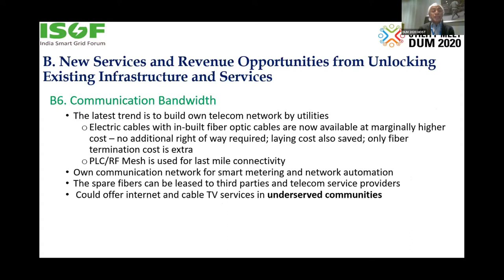I mentioned the latest trend in America and other places is utilities building their own telecommunication network. One major trigger is that the electric cable you lay comes with inbuilt fiber optic cables at a marginally higher cost, with no additional right of way required for laying the fiber and no laying cost. Only termination of the fiber is the additional cost. From the XLPE cable or distribution cables, it's only 2 to 3% extra cost for having fiber inbuilt, which gives you 48 to 96 fibers.